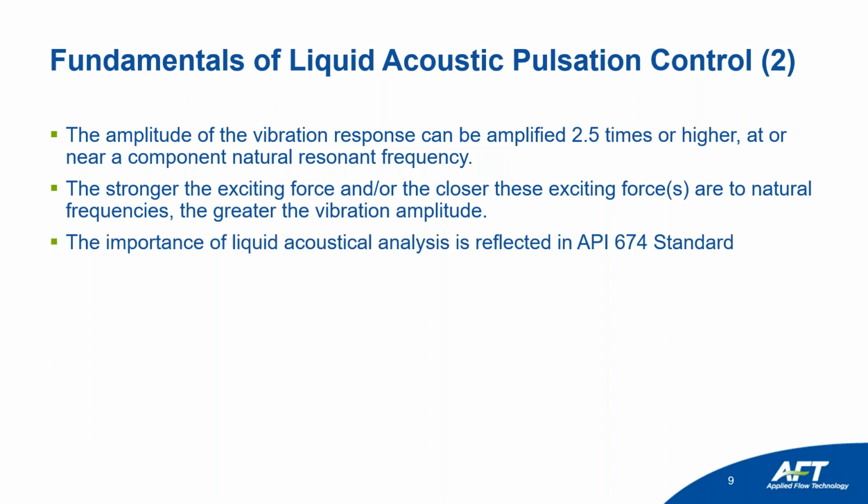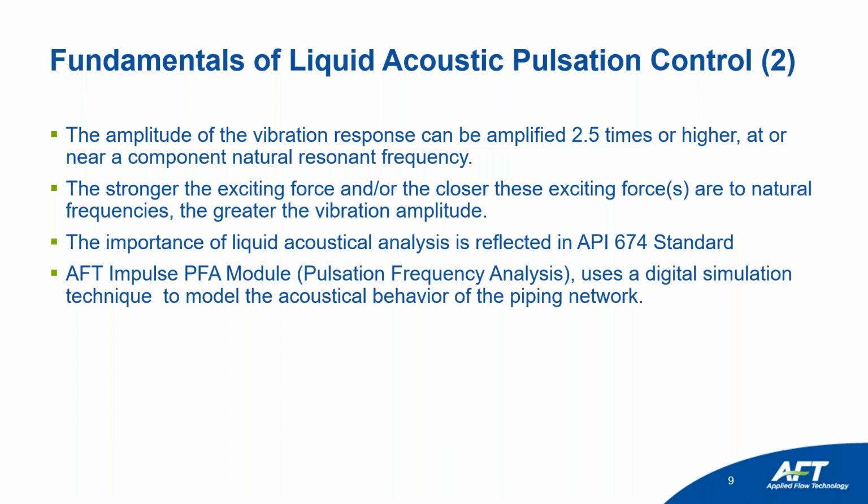The importance of liquid acoustical analysis is reflected in the API 674 standard. The AFT Impulse PFA module, pulsation frequency analysis, uses a digital simulation technique to model the acoustical behavior of the piping network.